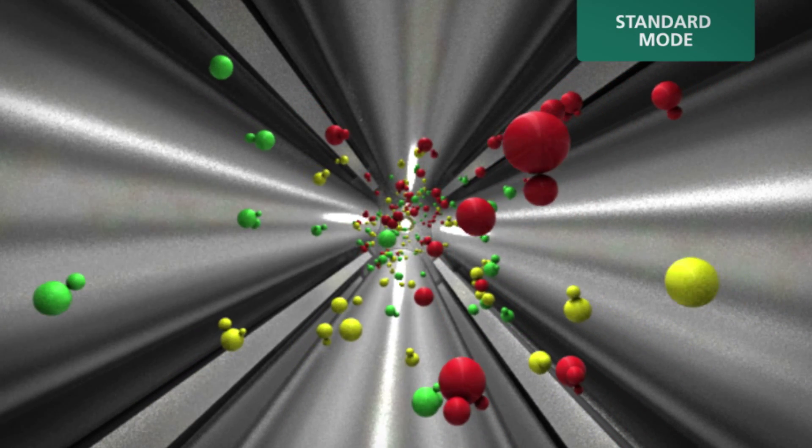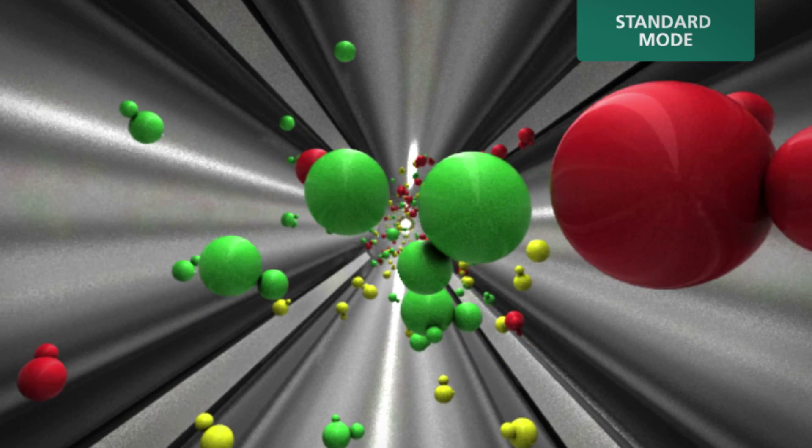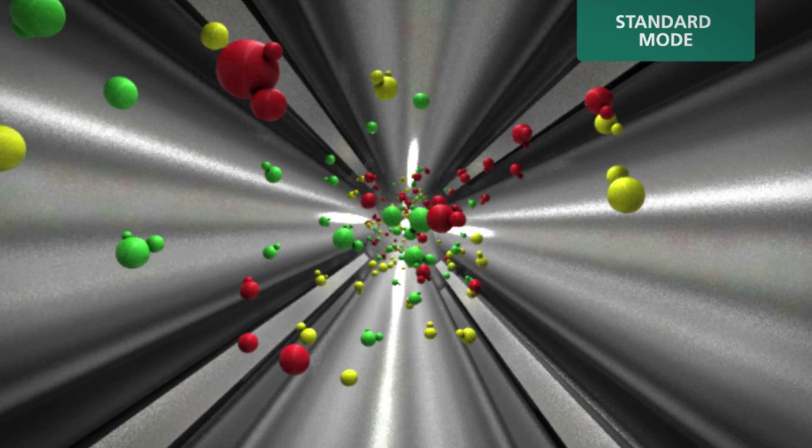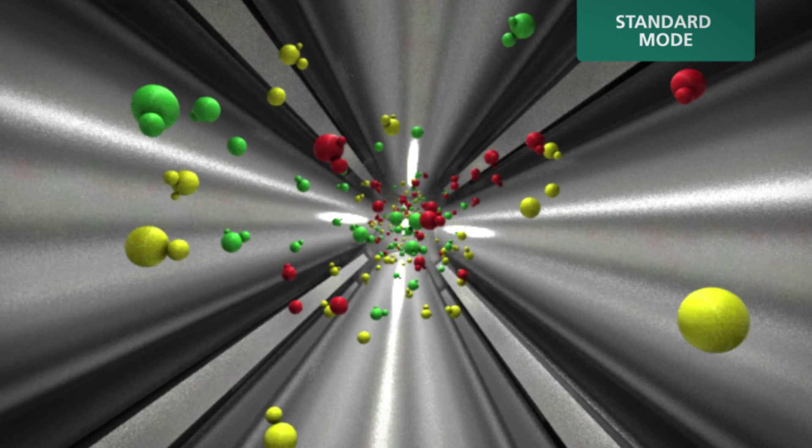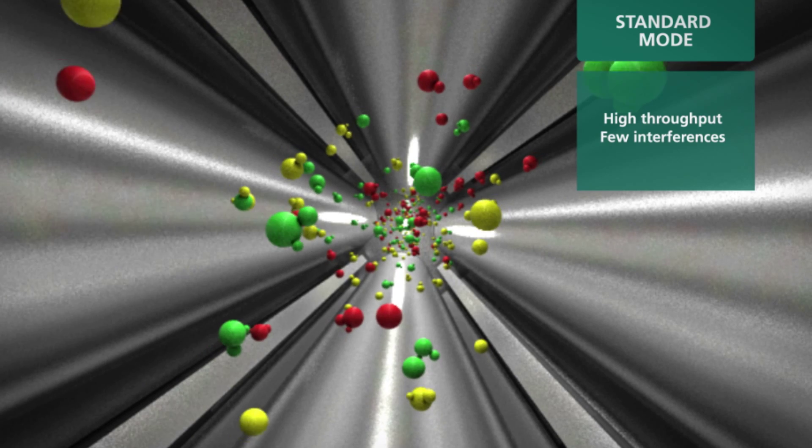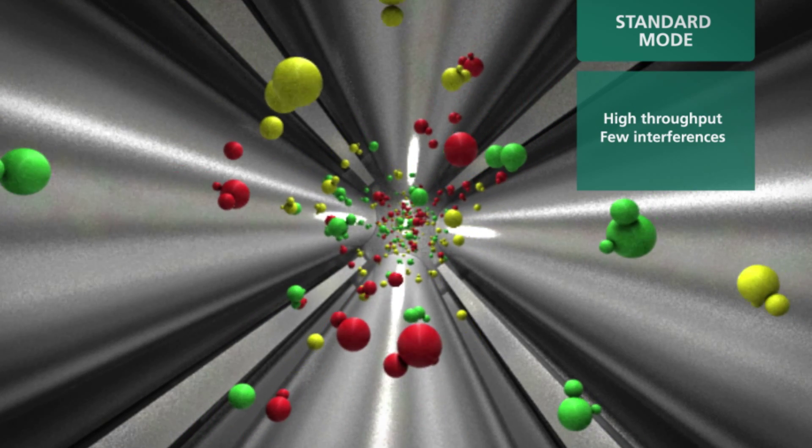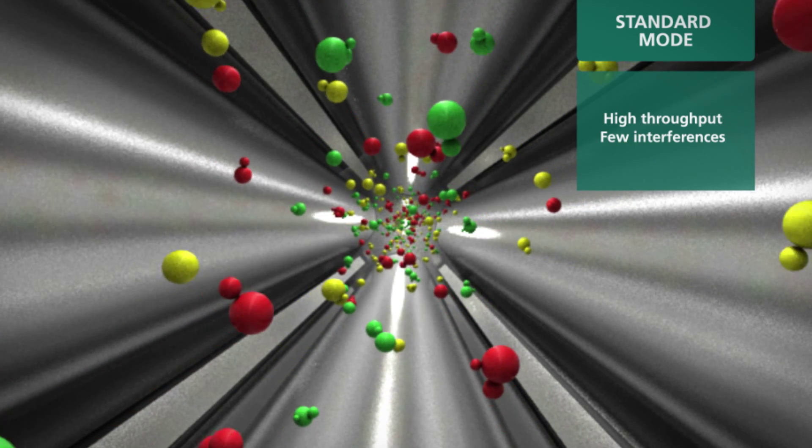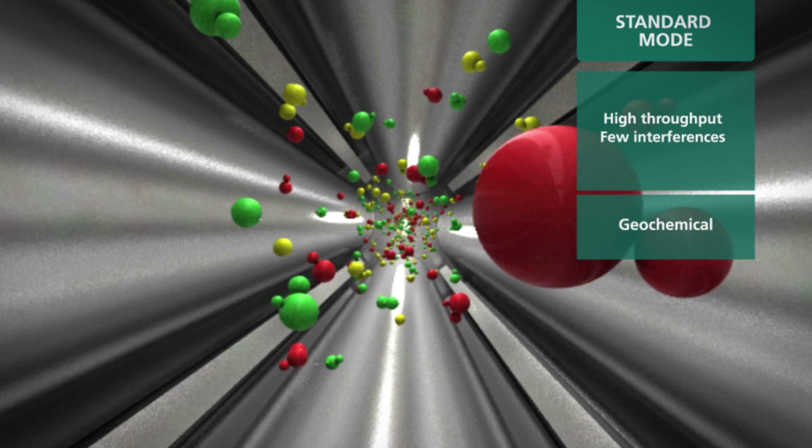In standard mode, the cell gases are turned off and the Nexion 300 ICP-MS operates like a traditional non-cell instrument. Ideal for many routine applications that have few interferences and do not require collision or reaction mode capabilities, standard mode offers excellent low mass sensitivity, making it particularly popular in geochemical laboratories.